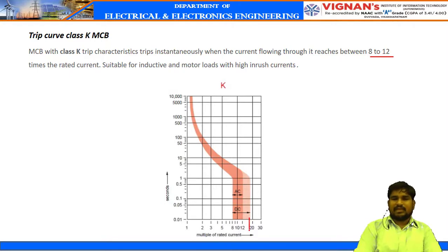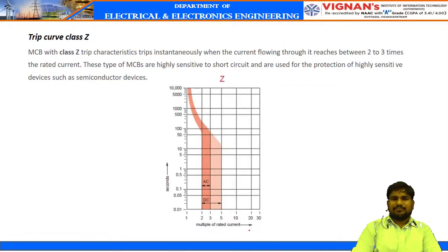Similarly, class Z MCB can be used for 2 to 3 times of rated current. It can withstand up to 2 to 3 times of rated current, and it can also be used for AC as well as DC. If you observe these two, the same circuit breaker can be operated at a higher amount of DC rather than AC. Because we know in case of AC we have other components like RMS, maximum, like that. But in case of DC, we have only average current. Right. Now let us come to the different characteristics here.